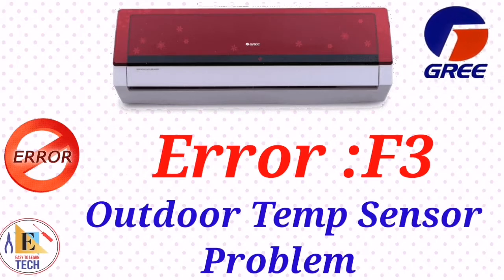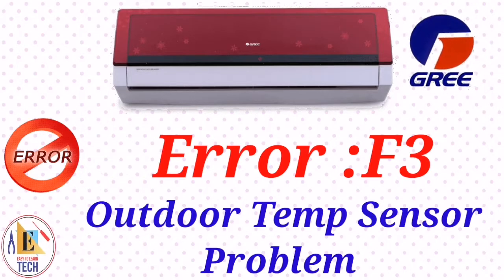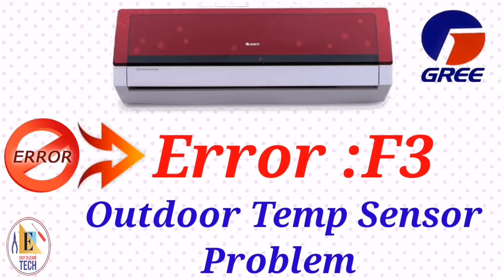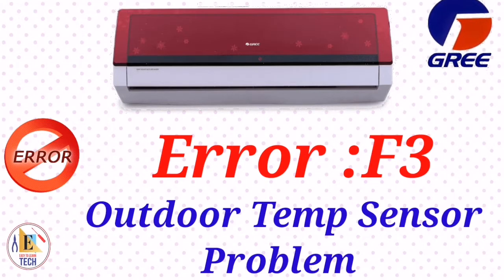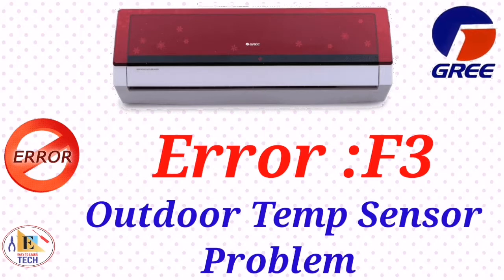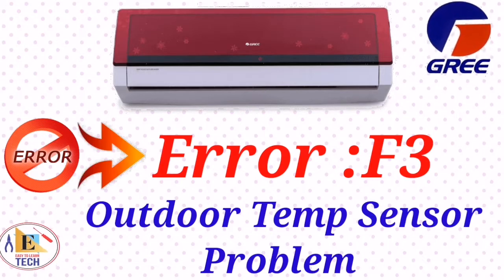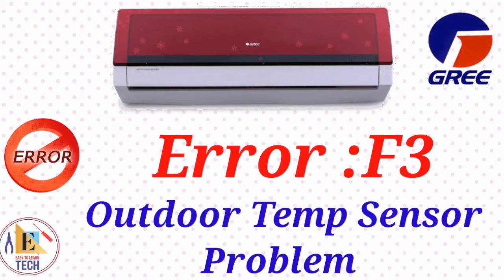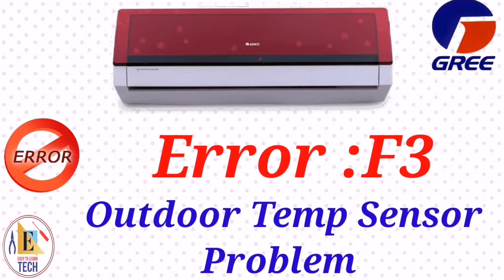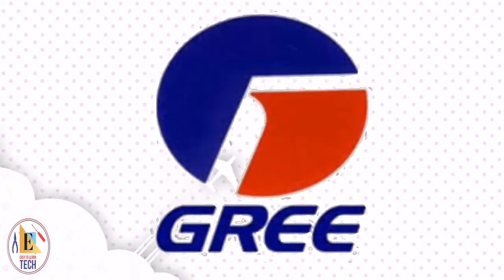And your unit will be in working condition. And if you see the resistance is good and again you are getting the same error, then you have to check the PCB, if the output supply from the PCB is coming properly or not. If the output supply is not coming properly, then you have to change the outdoor PCB. Our unit will be in working condition. Let's see the next error code.